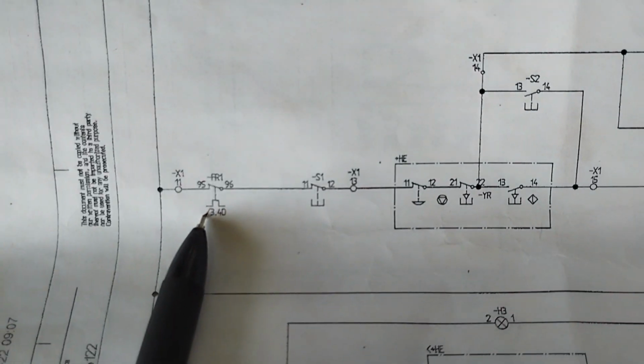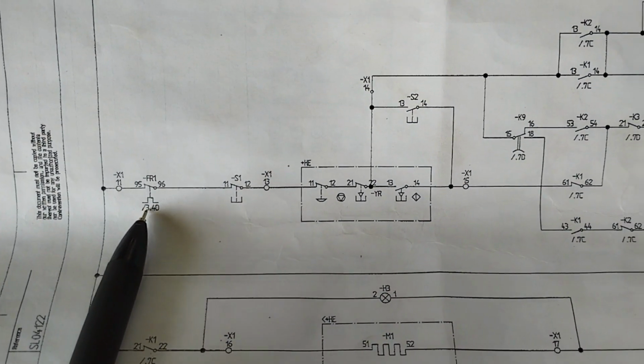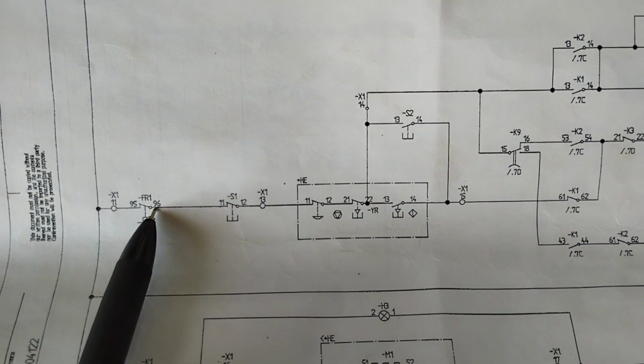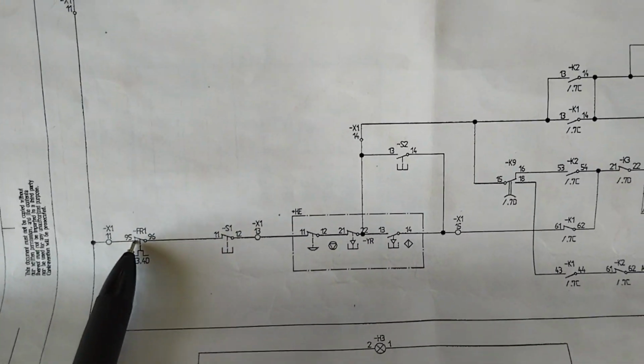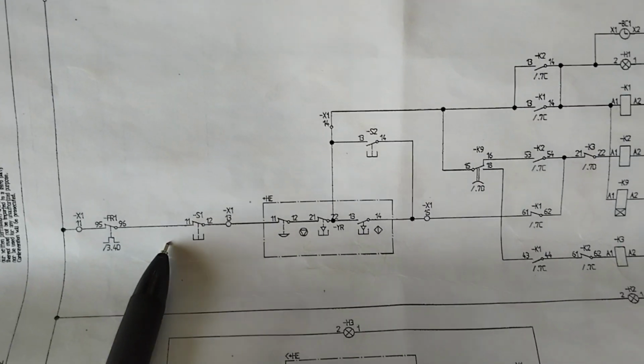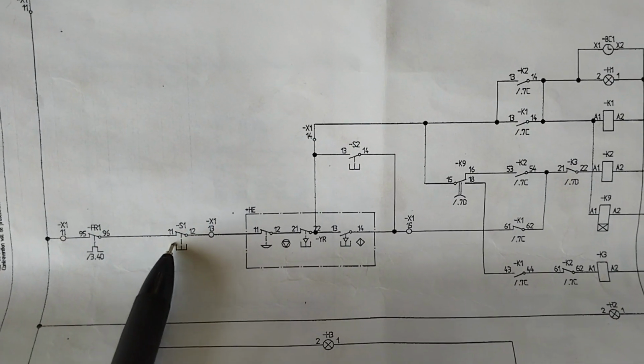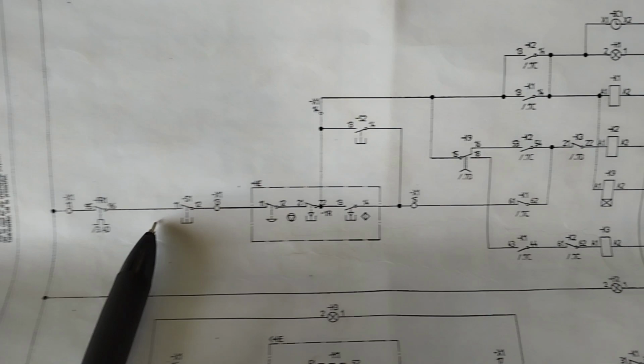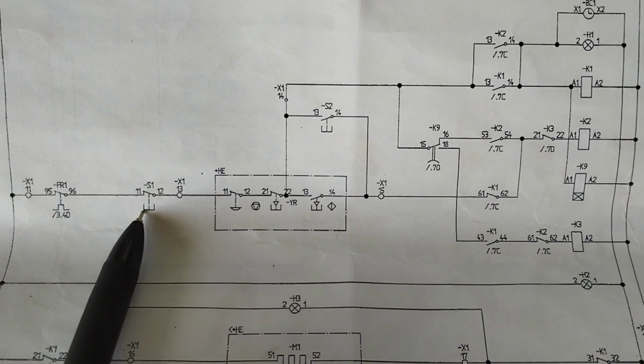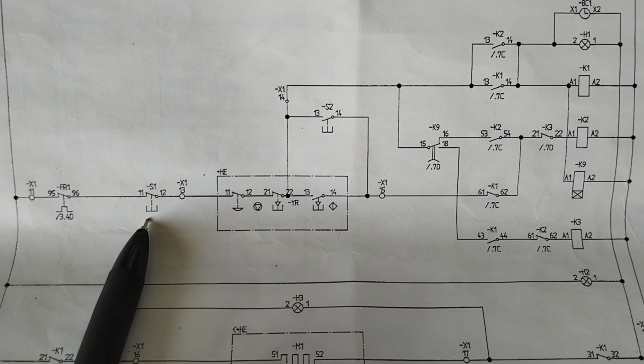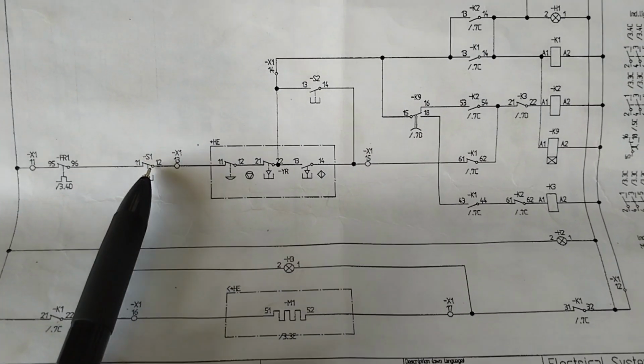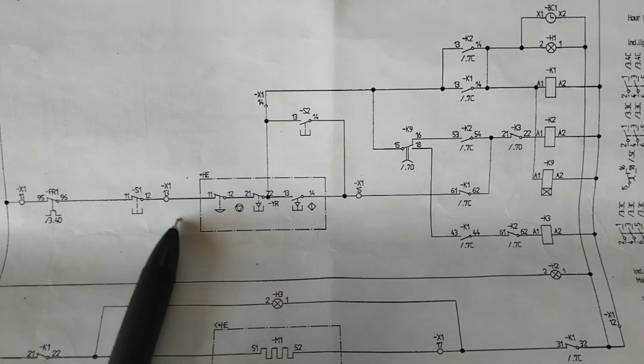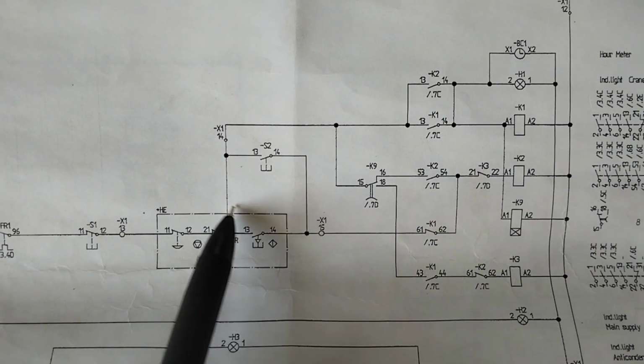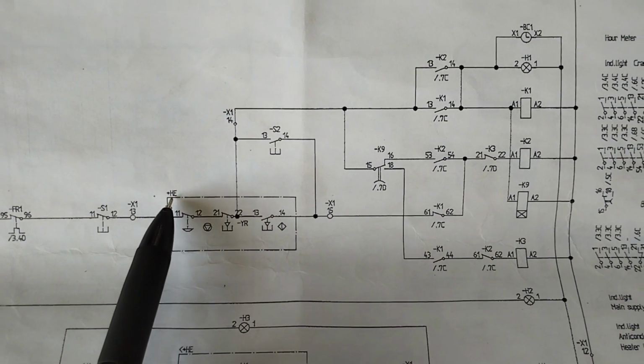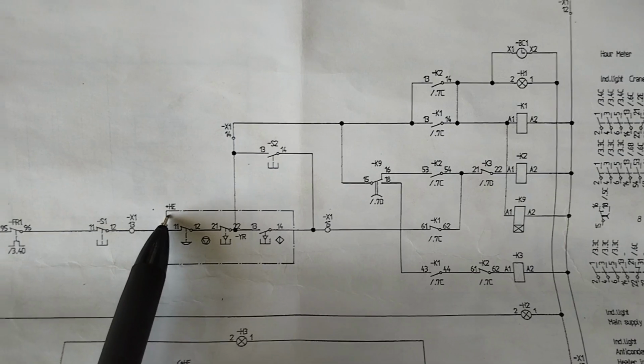95, 96. This is the OLR, overload relay. 95, 96, that everybody knows. This is the safety for the motor. If this is open, power will not go and power will not transfer, and your motor will not start. So this is the stop push button, S1. Okay, in case of emergency you can stop, or it is the normal stop push button, not only for emergency. So this is in the box. That box here is written HE in the crane control box. Okay, HE is the crane housing box.